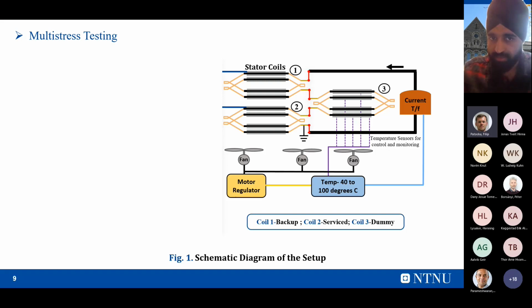Basically the copper inside is at ground potential. These copper strips, with these black color insulations, are clamped in two steel bars. So this is a steel bar, and inside that we have kept the copper strips. Now this entire setup is stressed by the current, and the temperature will shoot up and then go down with the help of fans, which are externally controlled by PLCs. The temperature will range from 40 to 110 degrees Celsius, depending upon the class of the insulation.